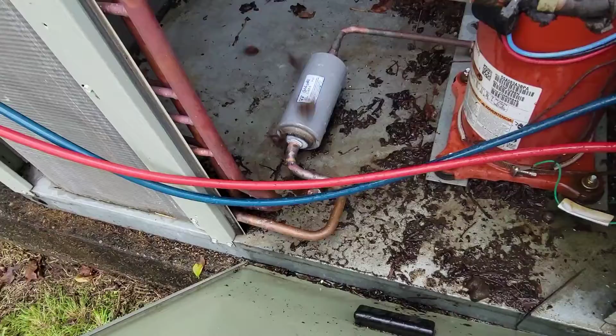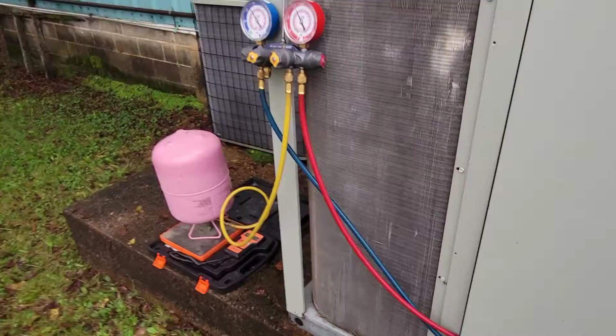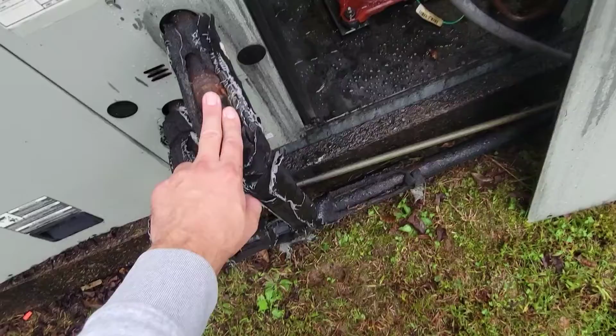Okay, so what I did was I changed the filter dryer. I flushed it with RX flush. I use nitrogen. Right now I'm charging, I got my scales on. And then I had to isolate the components. Look at that, 120 and 300, man, that's beautiful. I gotta get my temperature probe out, check superheat and subcooling.